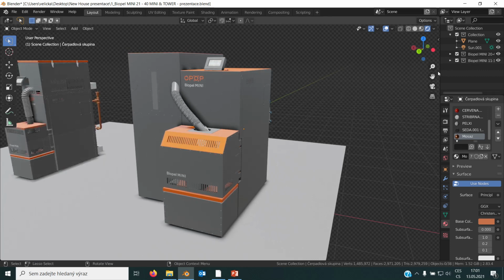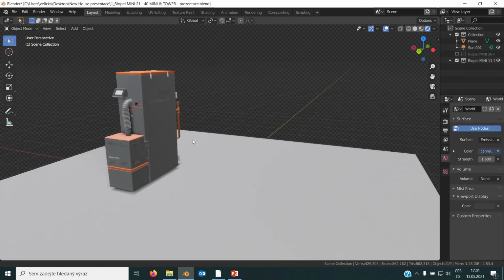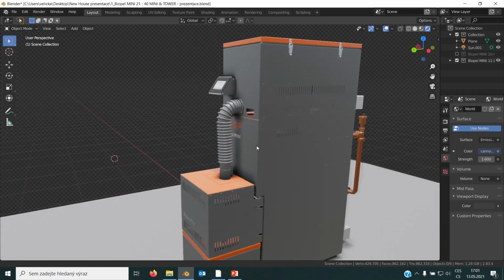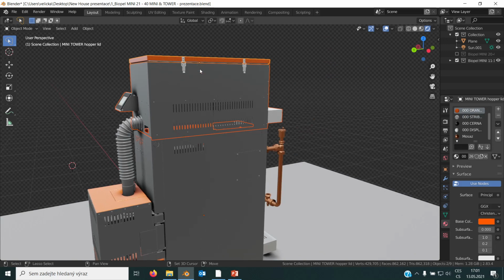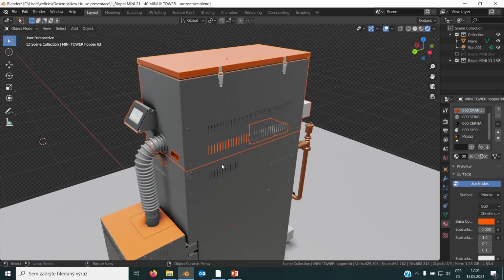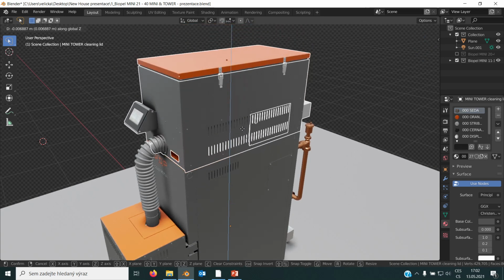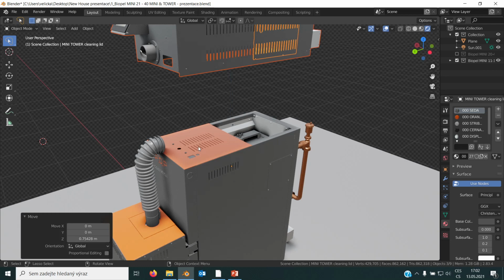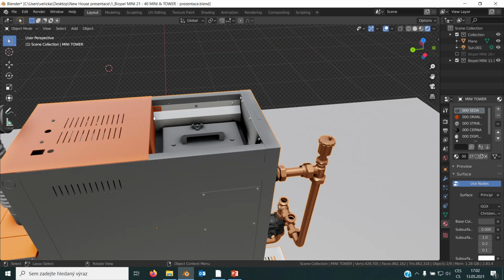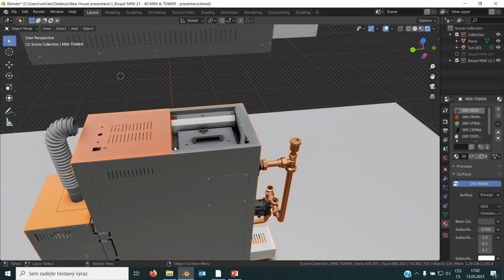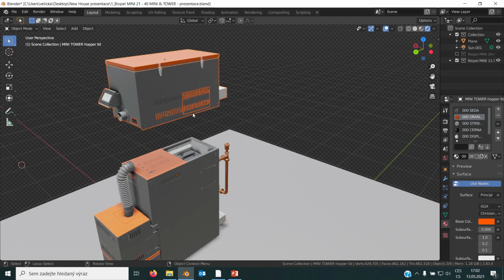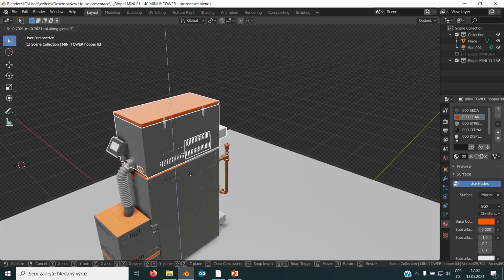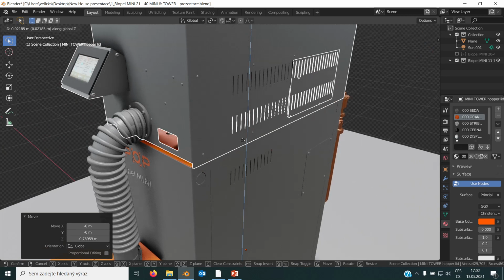And to compare it with the tower version, I would like to say a few things about the tower version. With the tank on the top, you have to do a few things when you install it. Okay, the tank itself, the pellet hopper itself, is only placed on the boiler. So there is no connection, it is just placed on the top of the boiler. But before you put the pellet hopper on the top of the boiler, you have to first remove the orange plate which is above the cleaning door. And the reason for that is that you want to be able to clean the boiler manually even when the pellet hopper is installed on the boiler.